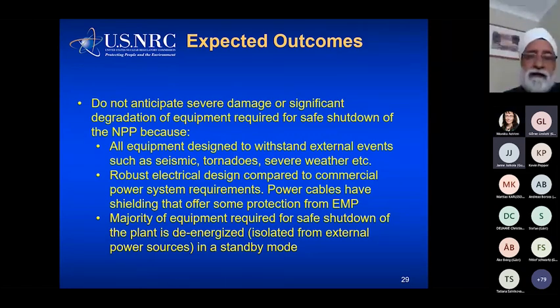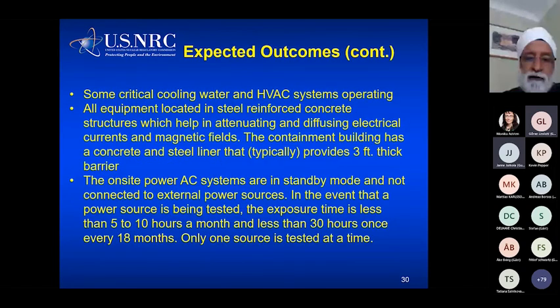We do not expect severe damage. We expect the equipment to survive, and we expect to safely shut the plant down because everything is in isolated mode. There is some critical equipment that's usually running, cooling water is running, HVAC systems are running, and because they're connected to the external systems, there could be some challenges there. We do not expect the reactor side to have any impact, or any adverse impact, because of the EMP.